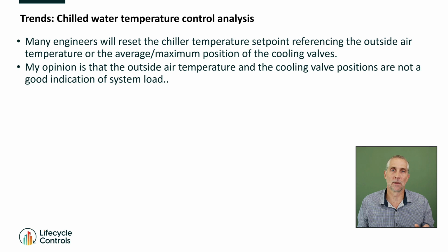And I can tell you right now, if we spent 8 hours on this, we could go through many chill water systems, AHUs, fan coils, VAVs, everything. Even things like VAVs and fan coils, we're doing the wrong thing. So understand that. An optimized control strategy doesn't always save energy. You didn't tune it properly. An optimized control strategy doesn't always save energy because it's wrong.